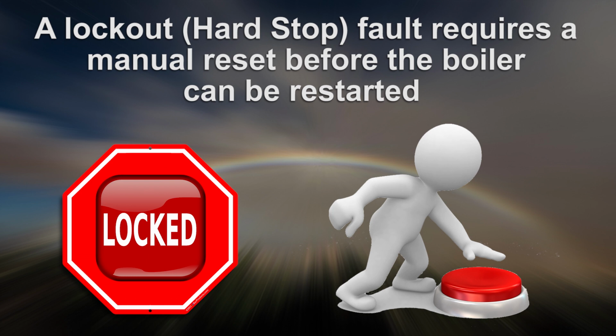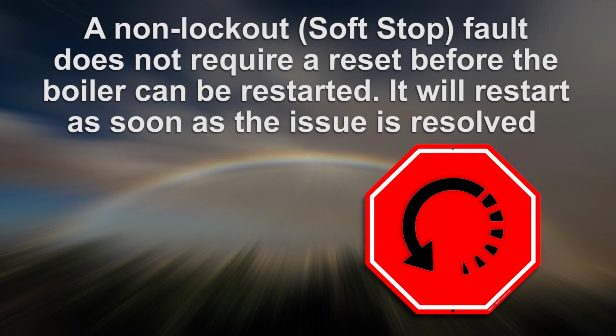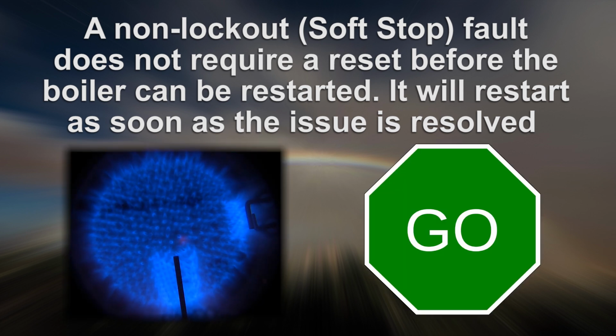A lockout or hard stop fault requires a manual reset before the boiler can be restarted. A non-lockout or soft stop fault does not require a reset before the boiler can be restarted. It will restart as soon as the issue is resolved.